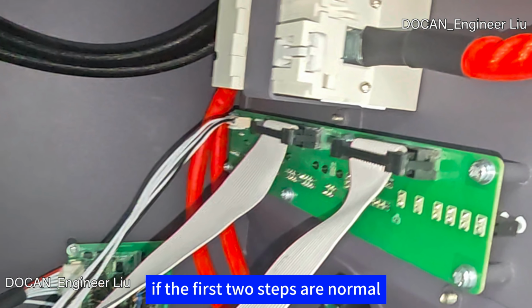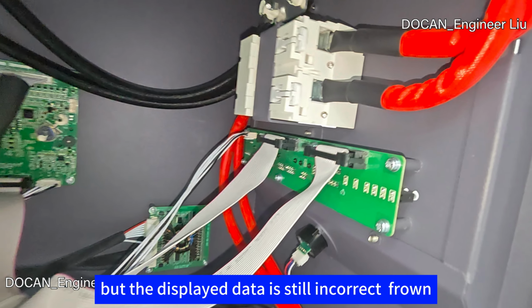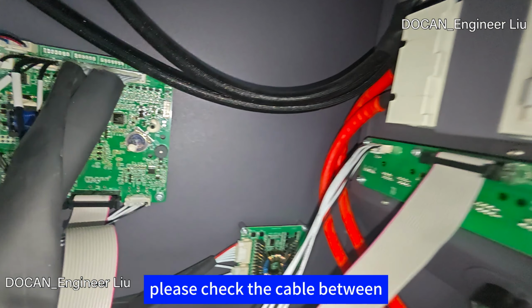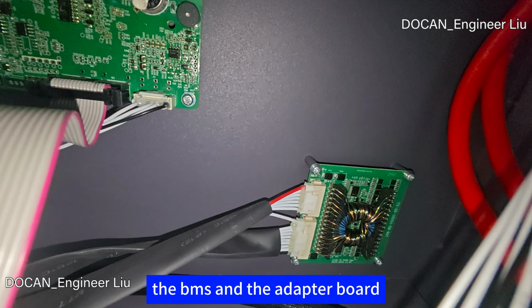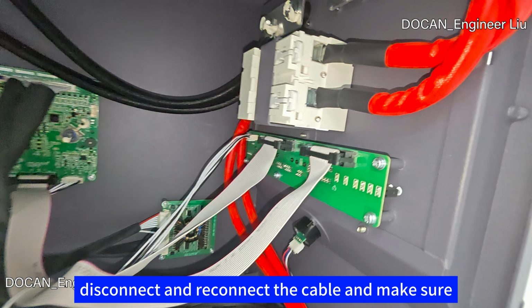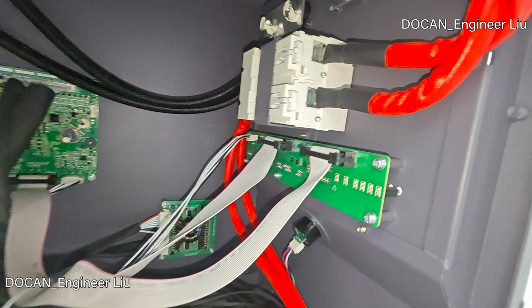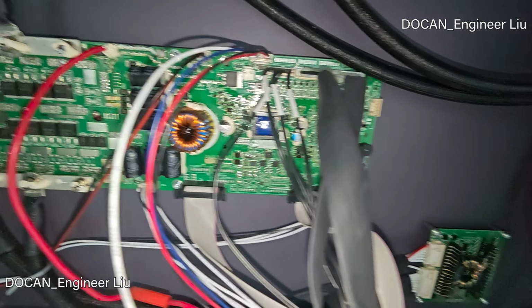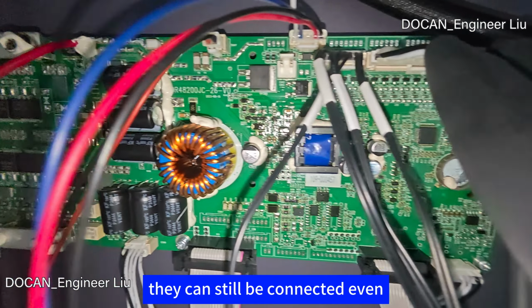If the first 2 steps are normal, but the displayed data is still incorrect, please check the cable between the BMS and the adapter board. Disconnect and reconnect the cable and make sure it is not installed in the wrong direction. Because some cables do not have a foolproof design, they can still be connected even when installed incorrectly.